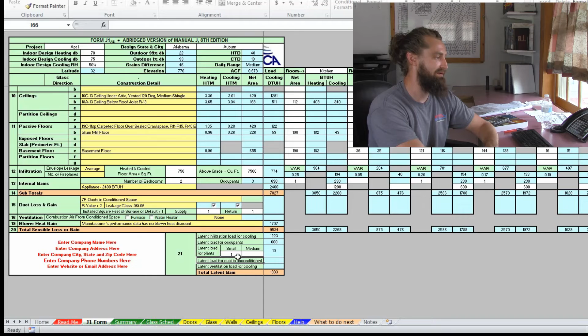That's that. Now we can go to our summary and see all of our heating and cooling loads room by room, and the CFM associated with each one for both heating and cooling. On the far right, it takes the larger of those two numbers, and that's what we use for our Manual D when sizing the ductwork for each room. So you can see our kitchen has the largest load. We need 174 CFM going to the kitchen to counteract the loads associated with it.